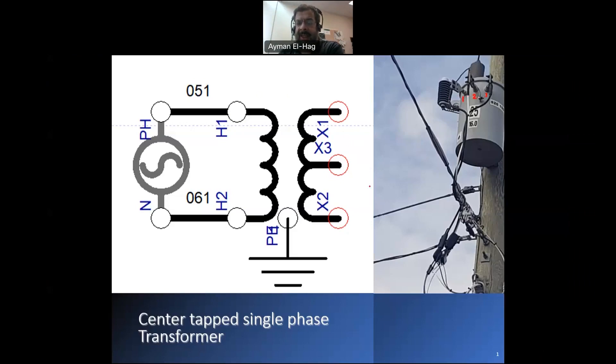This is a schematic diagram for this type of transformer. Again you have the high voltage side at the primary and then this is the low voltage side. You will have one, two, and three bushings or three terminals. We call this type of transformer center tapped single phase transformer, and this is very common in North America, especially for residential load.